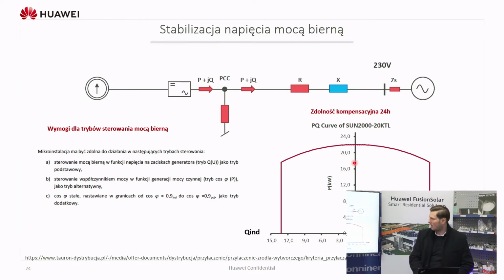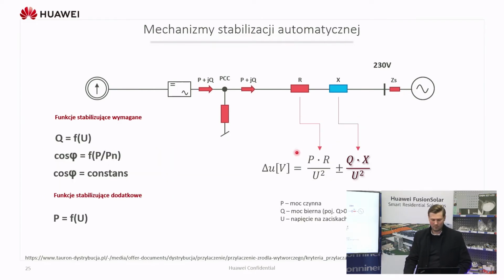So the voltage difference between this point and this point can be written with this formula. What we have an impact on is the active power, which we can regulate. Resistance, we won't change. Reactive power, of course, and reactance, which is also not adjustable. The voltage is the voltage from the grid, so we cannot regulate it at all.